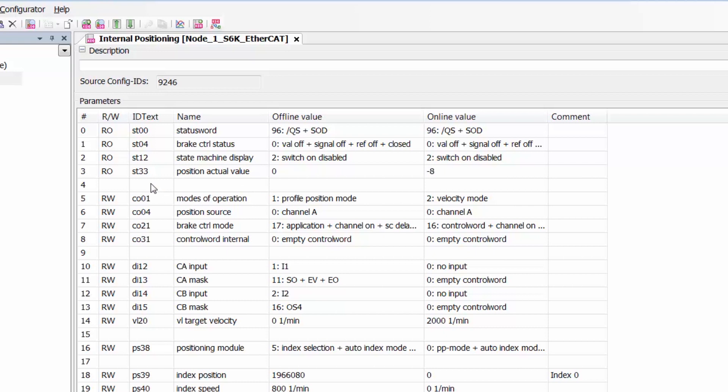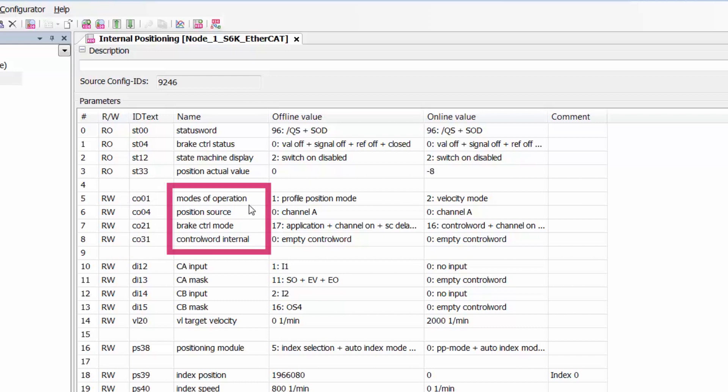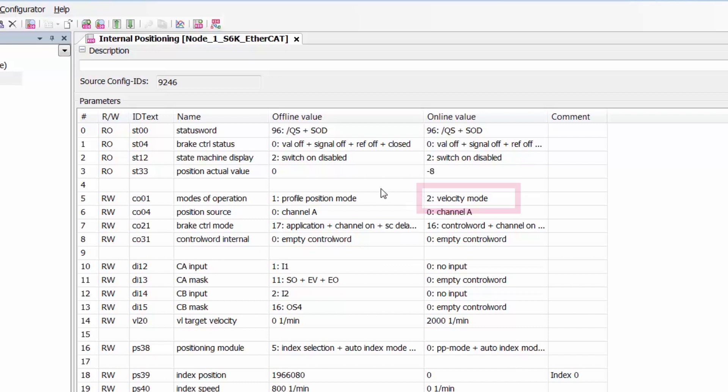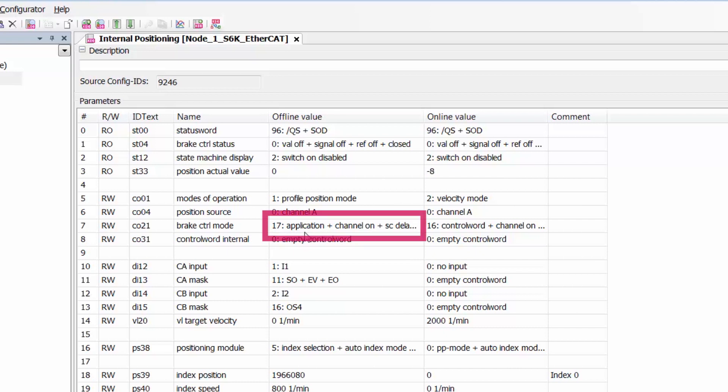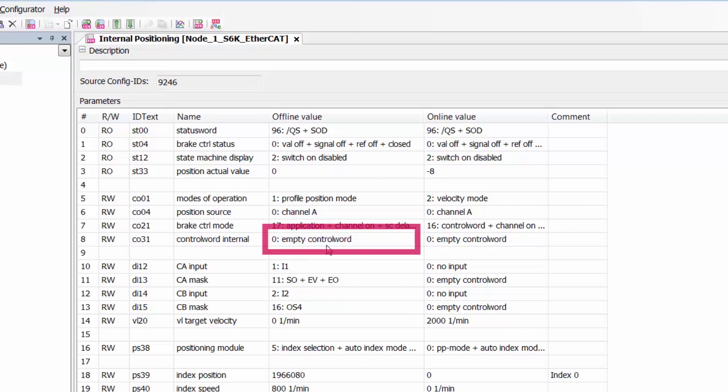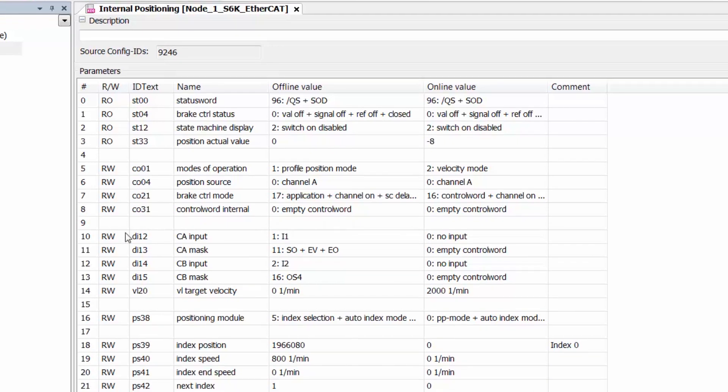Moving on from the status parameters we are going to look at our control parameters here. We have our mode of operation, our position source, our brake control mode, and our control word internal for the drive. We were in velocity mode to do the startup of our S6 but we are going to be in profile positioning mode here for internal positioning. We have channel A set as our position source so we can use the encoder feedback for positioning. We are going to change our brake control mode to applications so that when the drive is enabled properly the brake will automatically open and the brake will then close when the drive is disabled. We do not have to operate that through the control word. As of right now we have an empty control word but we'll describe how that will be manipulated here in our next set of parameters.